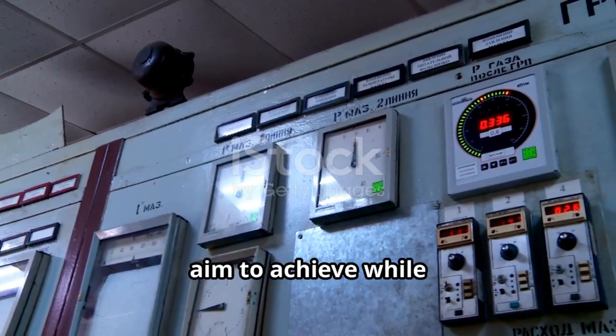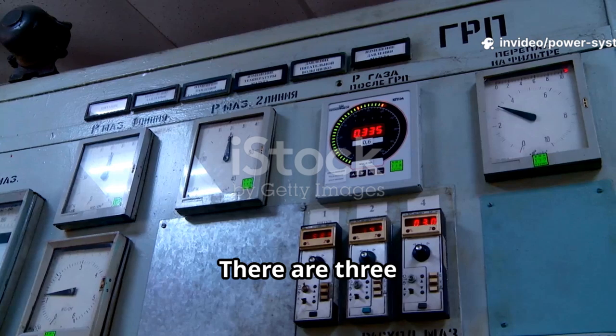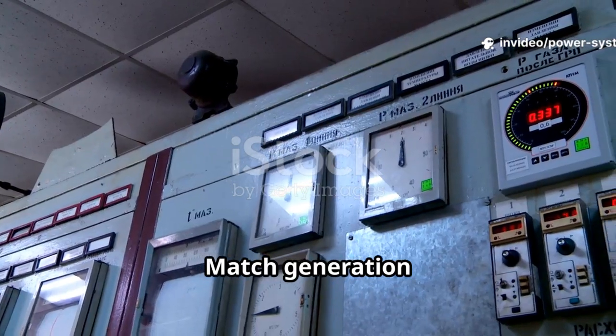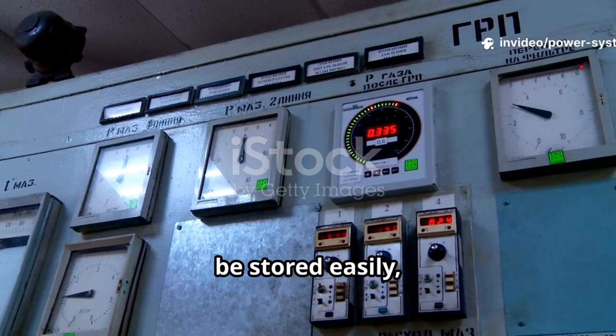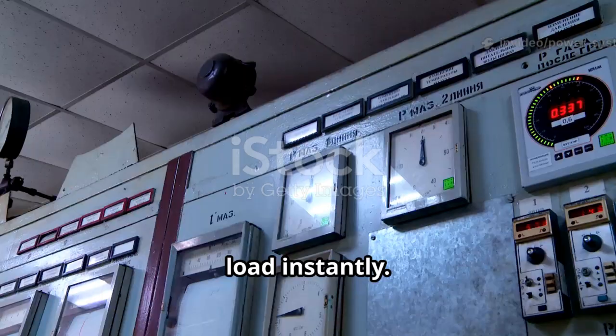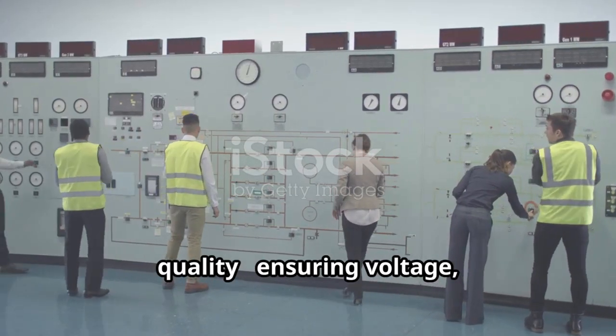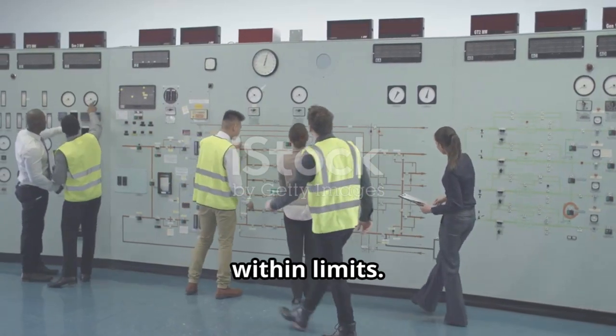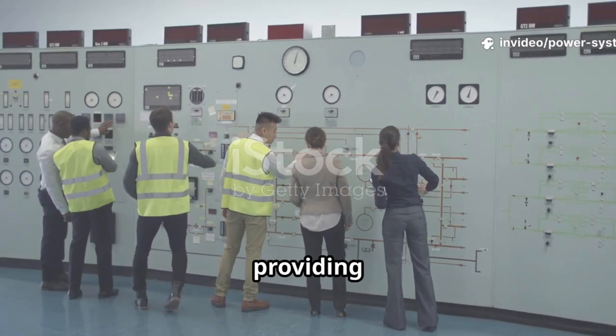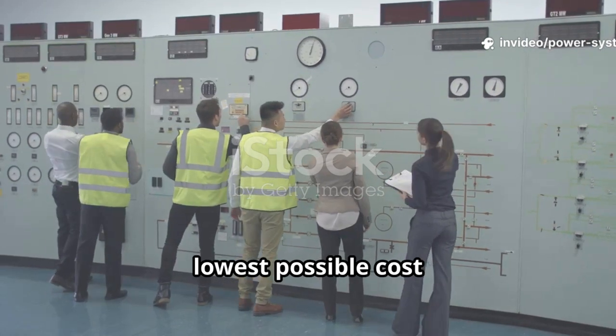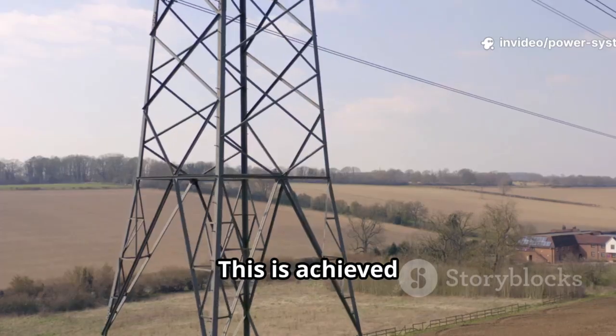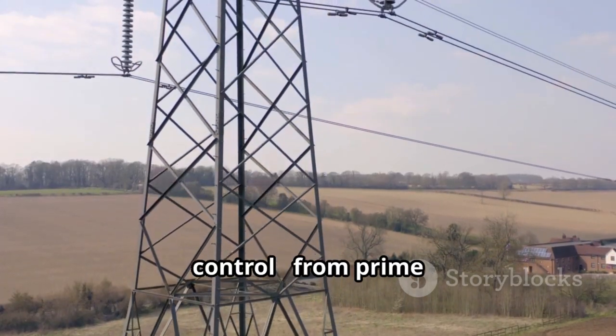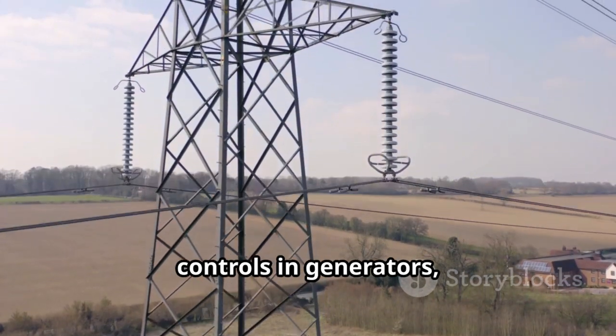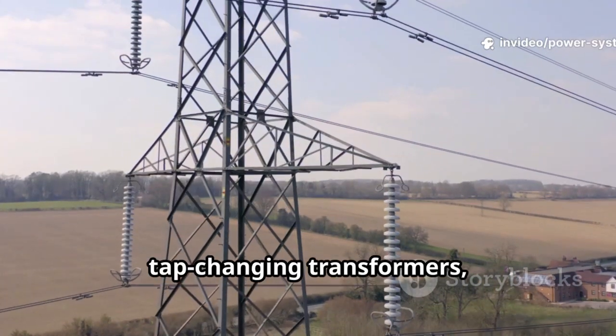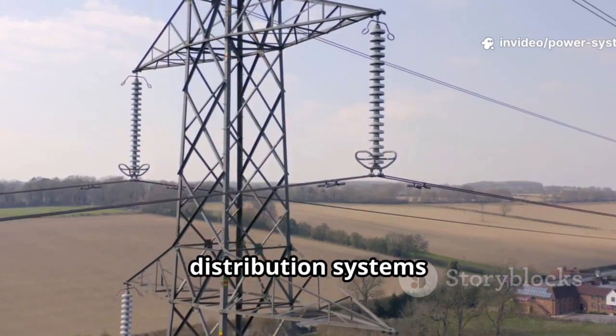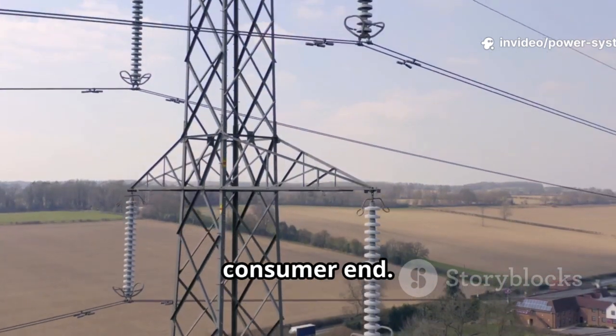So, what do operators aim to achieve while controlling a power system? There are 3 main objectives. Match generation with demand. Since electricity cannot be stored easily, supply must follow load instantly. Maintain power quality, ensuring voltage, frequency, and wave shape stay within limits. Operate economically, providing electricity at the lowest possible cost without compromising reliability. This is achieved through layers of control, from prime mover and excitation controls in generators to transmission devices like tap-changing transformers and down to distribution systems ensuring proper voltage at the consumer end.